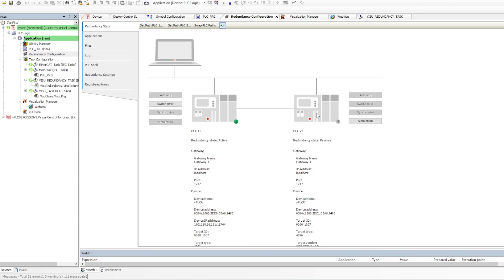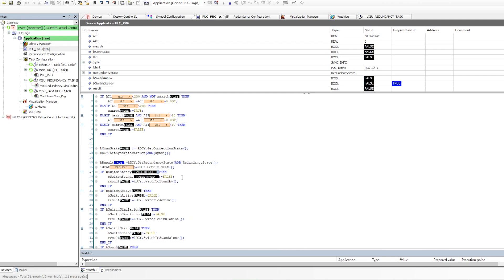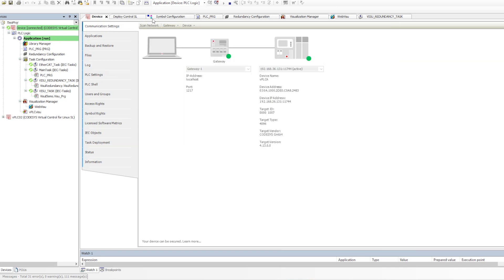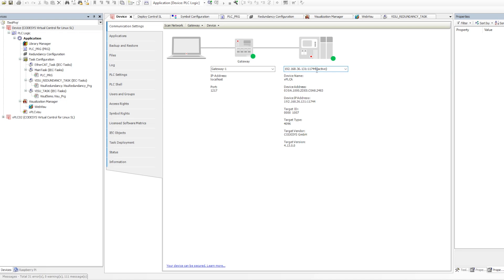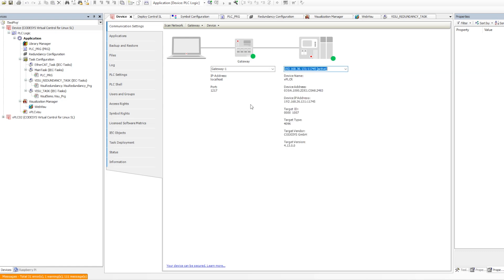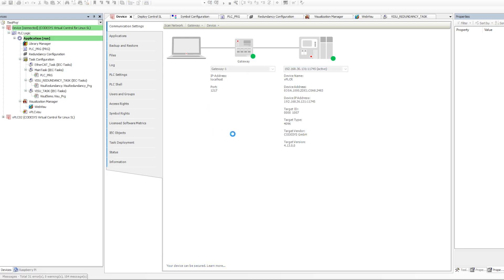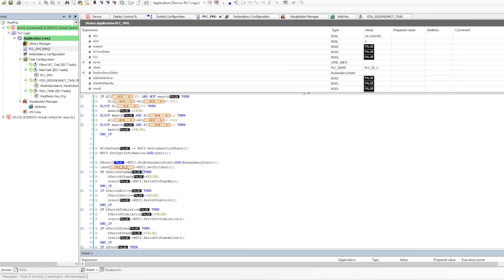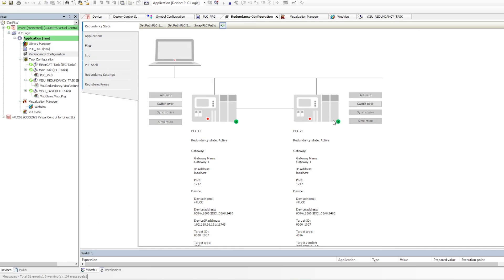Now I'll make PLC A go to standby mode. Going back online, you can see right now A1 is active and the second is passive. I'll switch the active one to standby — now you can see the first one becomes passive and the second becomes active. I go offline and connect to the second PLC; I don't need to download because the same application is already running on both PLCs.